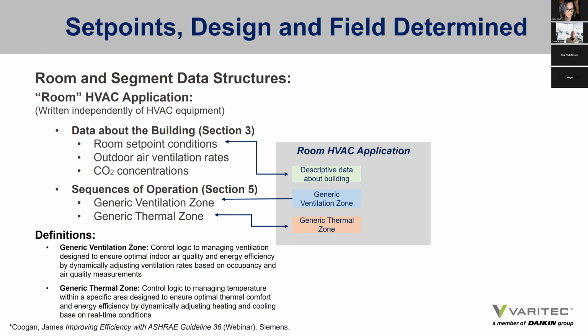Then in section 5 of Guideline 36, there's a review of generic ventilation zones and generic thermal zones that are defined, and we'll cover those terms more closely in a little while. All of this information is given to the zone, and that is called a zone group. A zone group is comprised of a group of zones served by a common air handler.